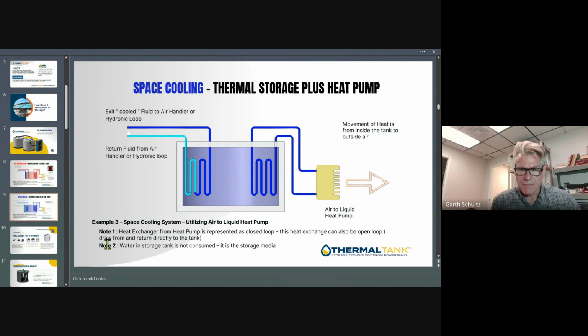Certainly. So, same air to liquid heat pump that's shown in the schematic. And instead of operating to pull energy from the atmosphere and put it to work as domestic hot water, just as a normal air conditioning system, a chiller, we pull from the interior of the building and then out towards the atmosphere to expel it. But those systems want buffering or storage between them, because otherwise there's a phenomenon called short cycling. That means you might have a demand on the hydronic system or on the HVAC or air handler system that says, oh, deliver me cold air. And the heat pump goes, well, I don't have enough capacity in the system. Or the inverse happens: you have the chiller wanting to make chilled water, but there isn't a demand on the other side. So you put in storage and buffering.